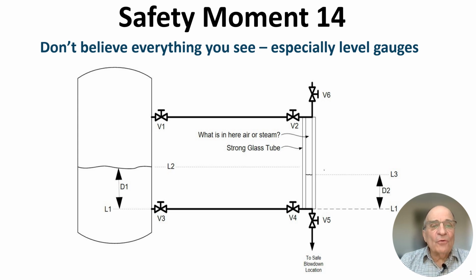Safety moment number 14. Don't believe everything you see, especially level gauges. They can be very, very deceptive, and they can be a cause of significant, serious accidents. Improper level gauge reading in the Three Mile Island plant was part of the cause of the partial meltdown of the nuclear reactor at Three Mile Island.